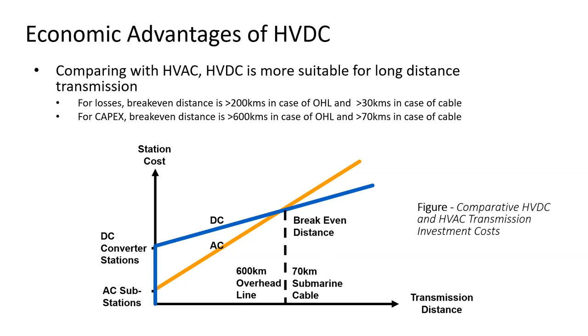In reality, this point is in fact a range, and it would change, for example, with transmission voltage. If the voltage goes up by hundreds of kilovolts, so for the same power, if instead of using 800 kV we start using 1.1 million volt, or 1100 kV, then this point could move left. And if the voltage is decreased by 100 kilovolt, then this point could move right.